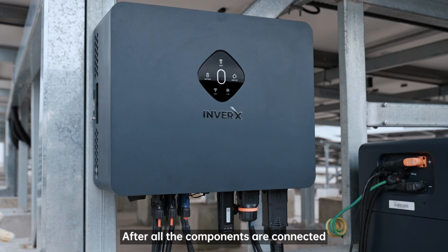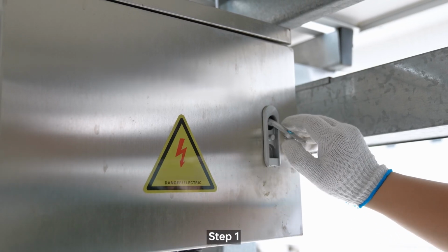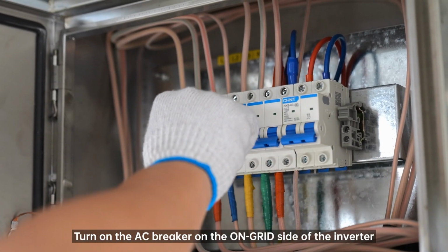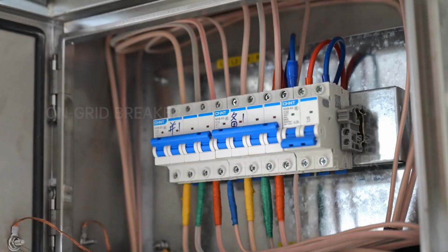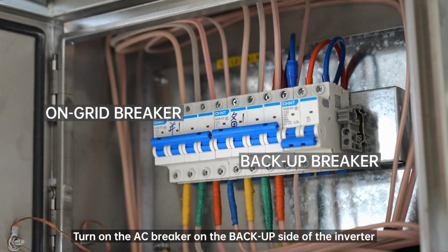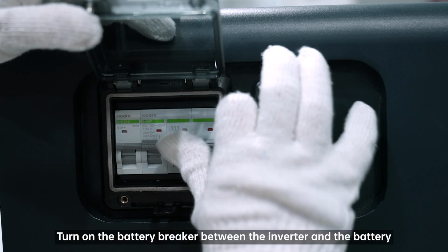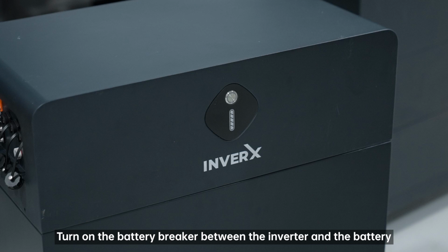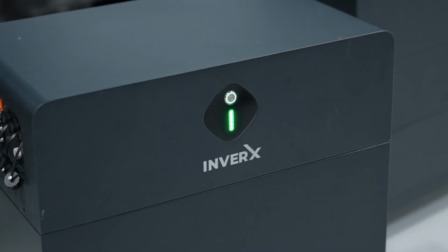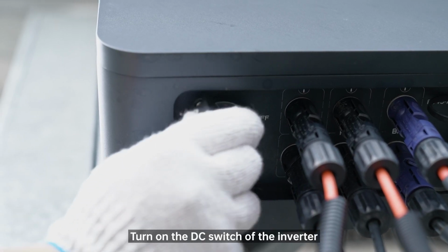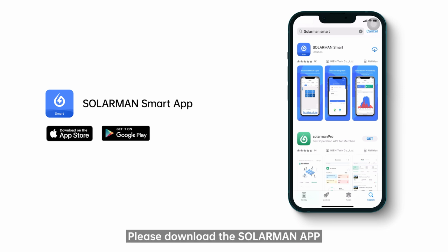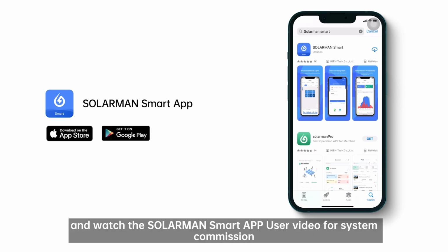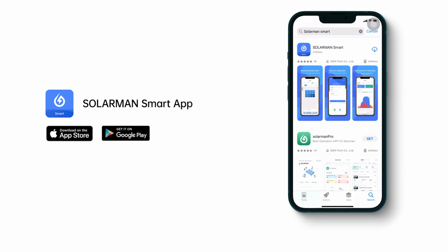After all the components are connected, we enter the system commissioning phase. Step 1. Turn on the AC breaker on the on-grid side of the inverter. Step 2. Turn on the AC breaker on the backup side of the inverter. Step 3. Turn on the battery breaker between the inverter and the battery. Step 4. Turn on the DC switch of the inverter. Please download the SolarMan app and watch the SolarMan Smart App User video for system commission.